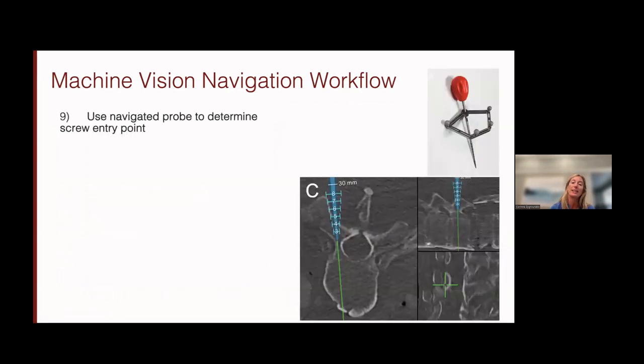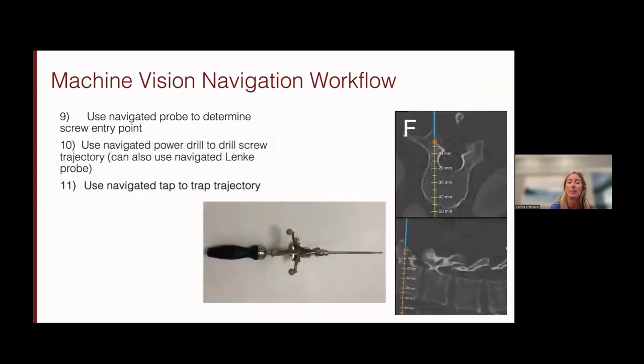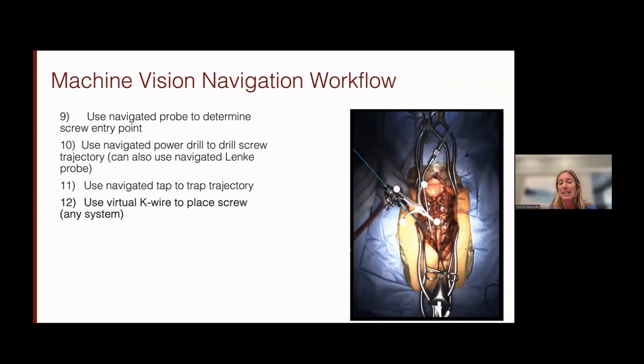At this point you bring in your instruments — navigated probes, navigated taps, navigated screw inserters — with an image on your screen very similar to other navigation platforms. You can use a navigated Lenke probe, a navigated tap to tap your trajectory, and because the system is screw agnostic you can use any type of screw. There are also virtual K-wires that show two lines in two planes so you can line up your instrument and place your screw.